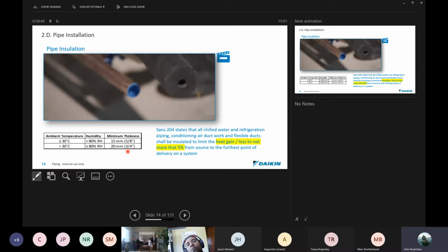What is interesting to note is what the SANS 204 states, and this is a South African guideline. For all chill water and refrigeration piping, conditioning, air duct work, and flexible ducts shall be insulated to limit the heat gain or heat loss to not more than 5% from the source to the furthest point of delivery on a system. Now, if you consider a system that might be operating at around 75, 80 odd degrees, that is in the region of about 4 degrees, the 5%. Just keep that in mind, because we're seeing guys insulating pipes with 1/4 inch and 3/8 inch Armaflex. It's not acceptable even by our local standards.